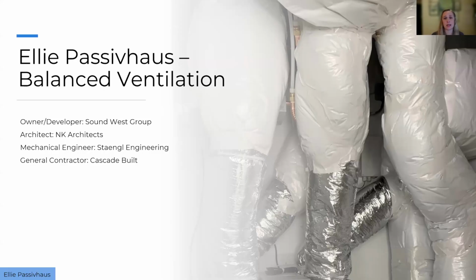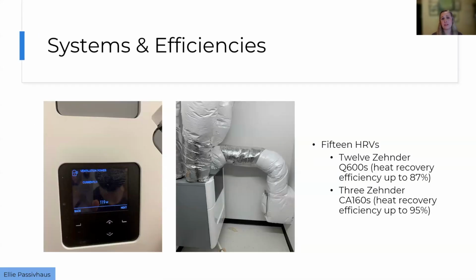It's a combination of interior and exterior access units, and it's 5 wood frame stories over 2 type 1A construction, and utilized a hybrid of centralized, floor by floor or horizontal zoning of HRVs, in addition to unitized systems, or individual units, for those 3 live-works on the first floor. And I'll show a graphic for how things are split in a moment here. So there were a total of 15 HRVs used for this project, 12 for servicing multiple units or groups of units, and then 3 smaller ones that were used for those live-works.